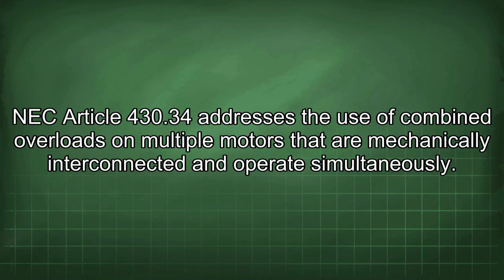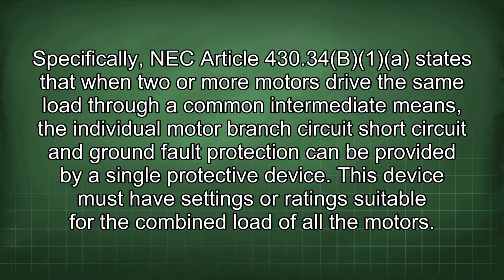NEC Article 430.34 addresses the use of combined overloads on multiple motors that are mechanically interconnected and operate simultaneously. Specifically, NEC Article 430.34(B)(1)(a) states that when two or more motors drive the same load through a common intermediate means, the individual motor branch circuit, short circuit, and ground fault protection can be provided by a single protective device.